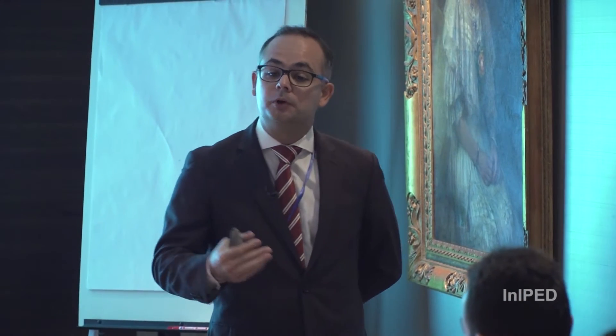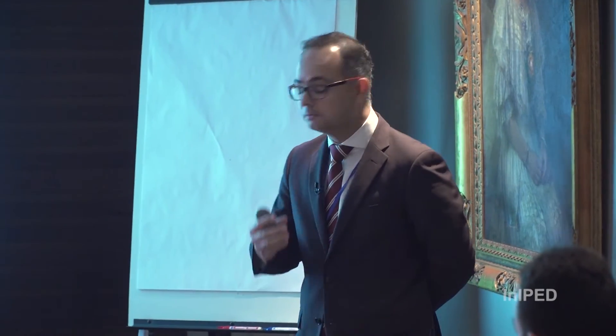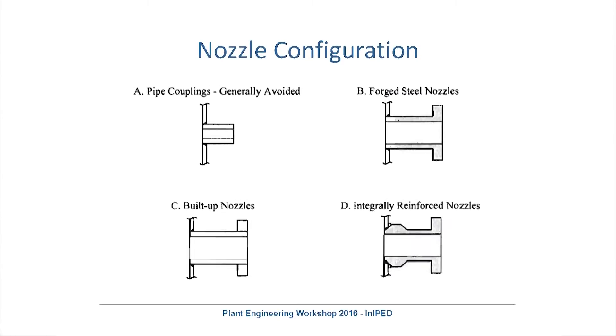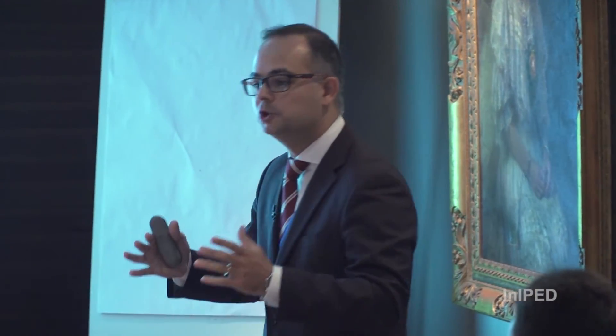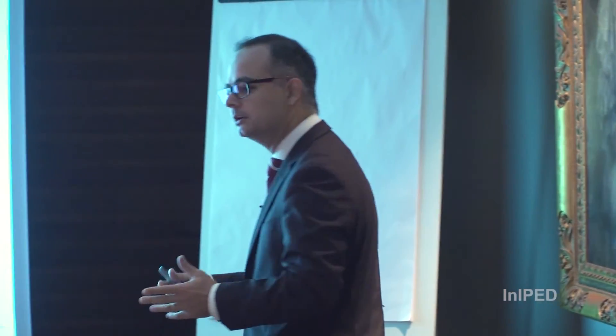We have different nozzle configurations that we are going to be able to choose from in order to design our pressure vessel. We have pipe couplings, we have forged steel nozzles, we have built-up nozzles — this is the most typical configuration. We are going to be talking about this later in the next slide. And we have integrally reinforced nozzles — a solid piece of metal that is going to be tailored according to every specific design. Most expensive, more reliable.